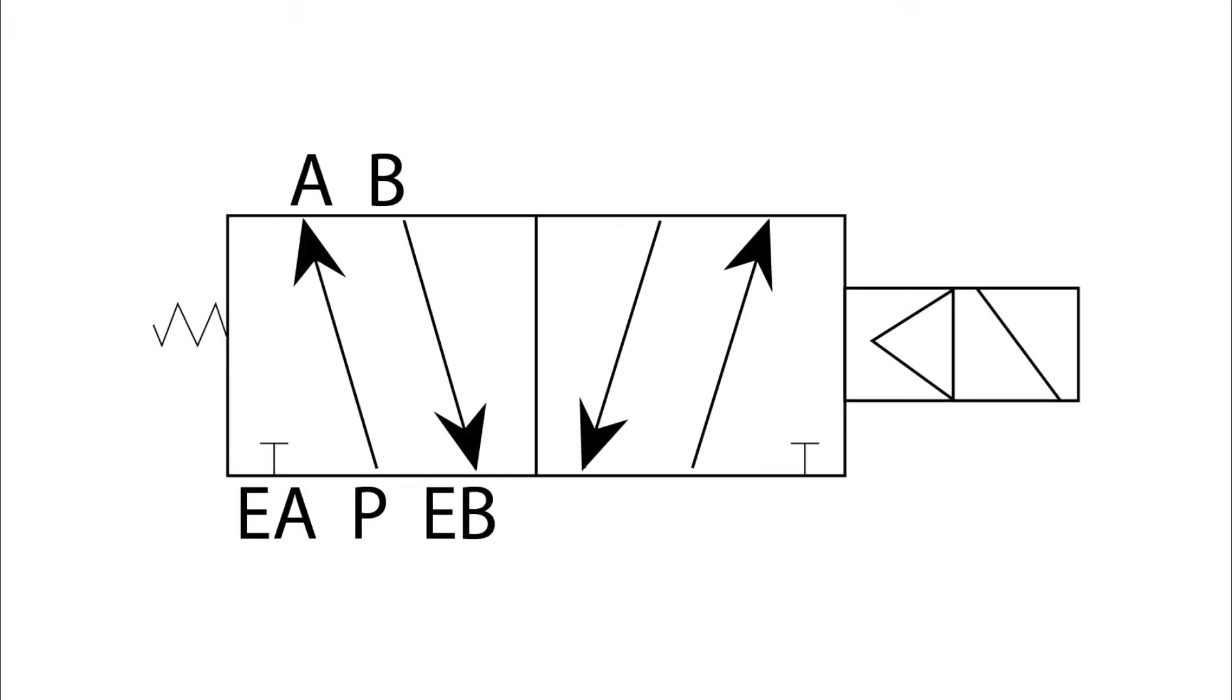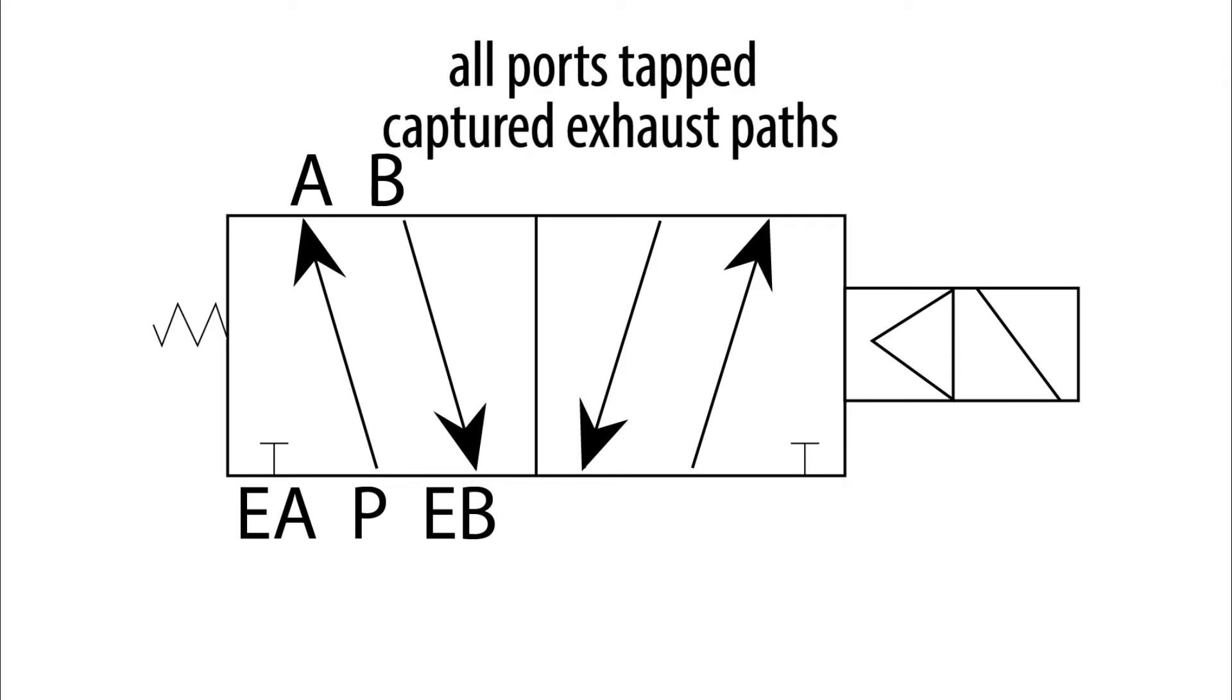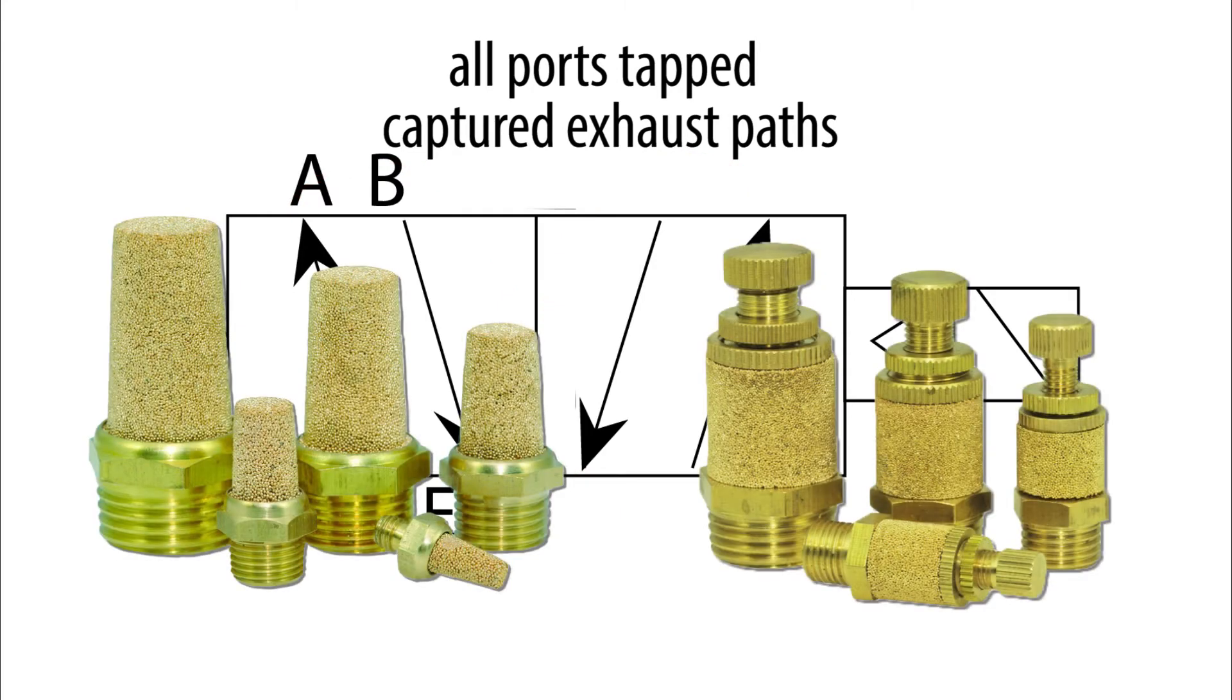So here's how we do this. Maximatic valves all have ports tapped and captured exhaust paths. This means two things. First, the valves have independent flow paths from output to exhaust, while other valves can sometimes use a common exhaust port. Second, the exhaust ports are tapped for use with mufflers or speed controls.